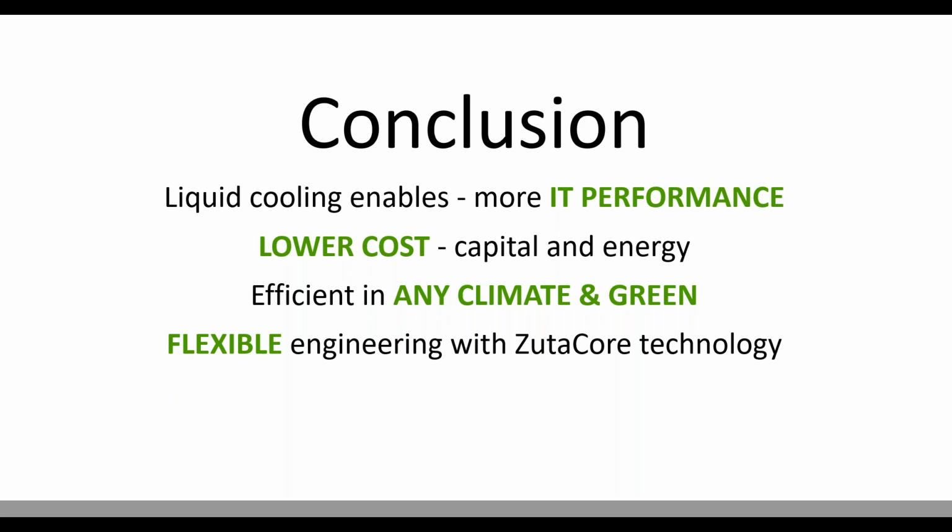Okay, no, that's good news. All I can add, and I'm not an uptime engineer, is that Uptime's design rules, if you like, are agnostic to the technology. So the question is always how you can fit that technology into the framework of continuous cooling requirement and fault tolerance. And of course, there's always the question, which could be up for debate from my experience, of what is a maintained component and what can be viewed as something that you don't have to maintain. But that's a longer conversation, and I want to be respectful of everyone's time.